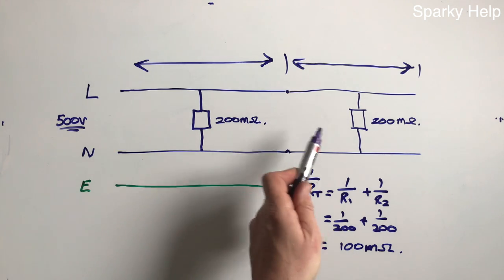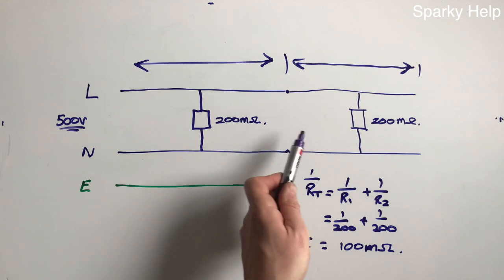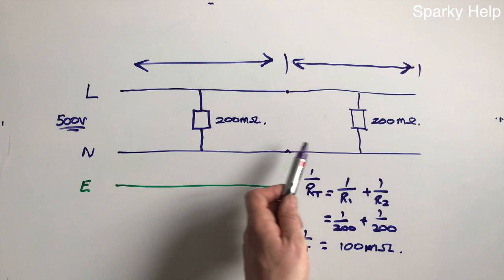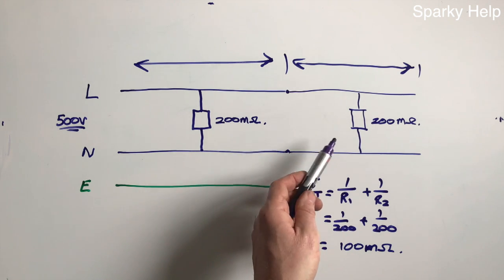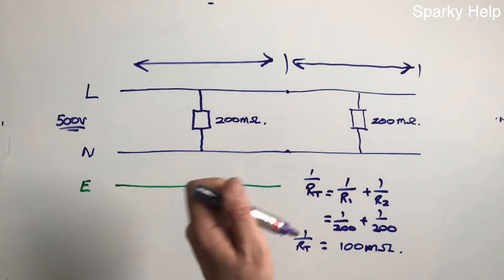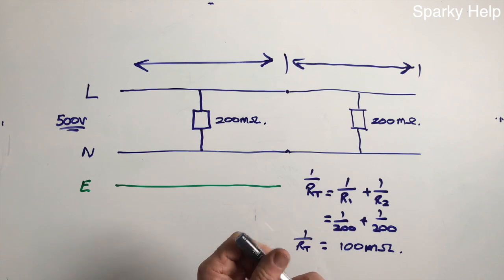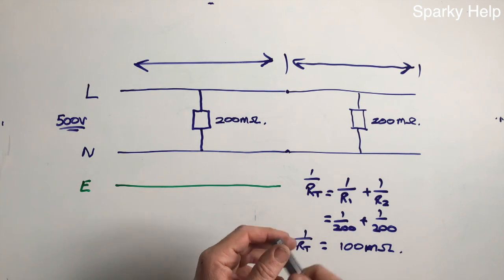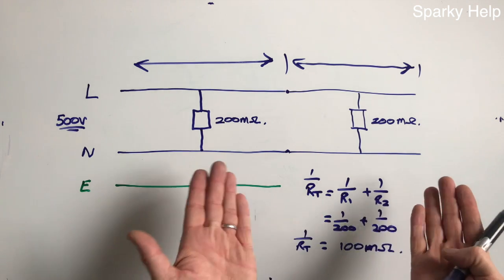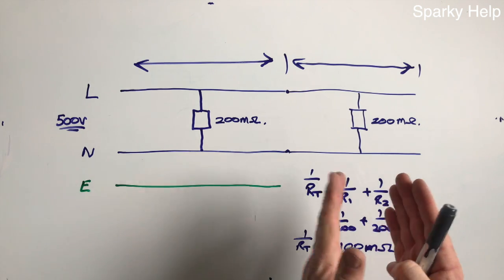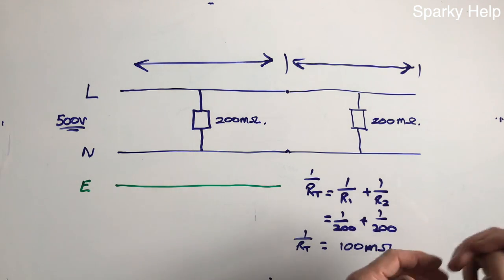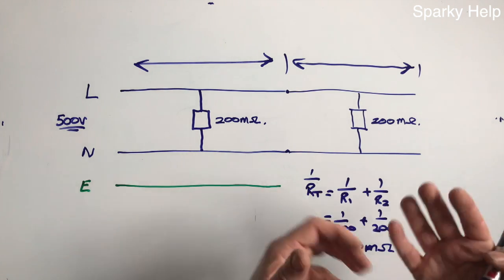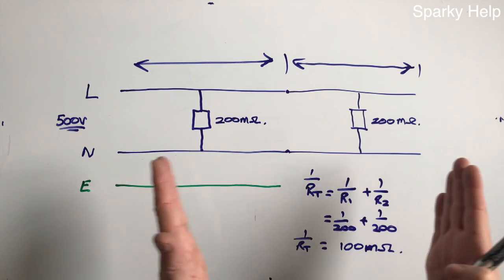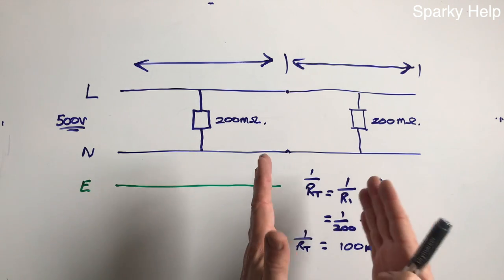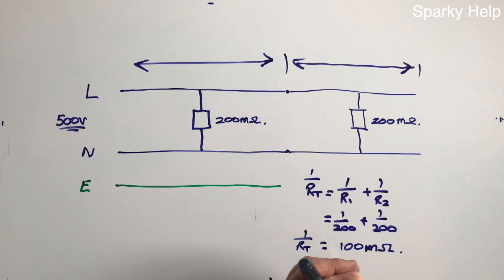So with this installation, what you're basically going to end up with, if you double the length of these cables, is that the insulation resistance comes down. The same is true, because what it would like you to do is test all your circuits in one go. So if these are all individual circuits, circuit 1, circuit 2, 3, 4, 5, 6, 7, and each one of them is 100 mega ohms, when you test them collectively, they will reduce proportionally for the amount of cable you have installed.